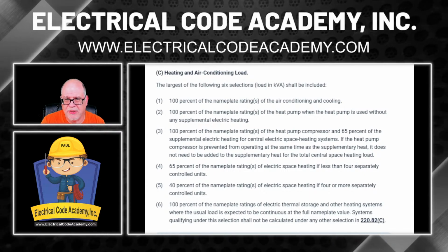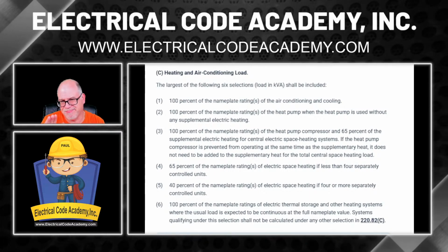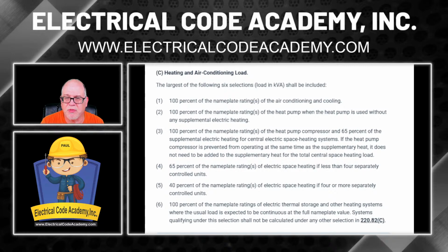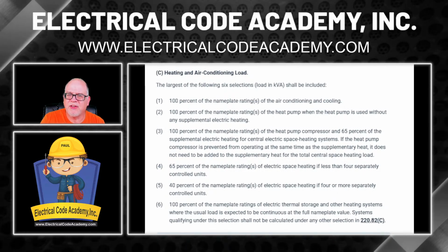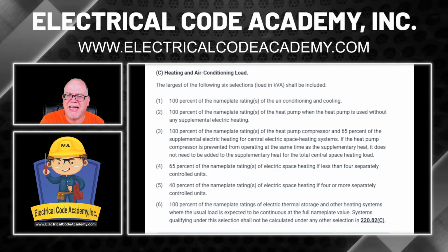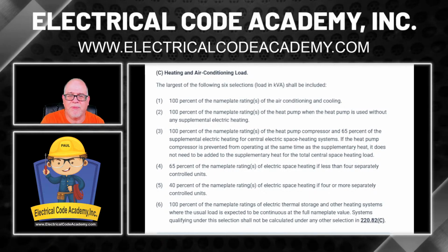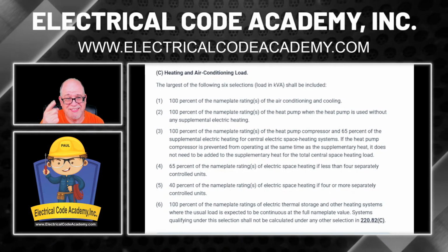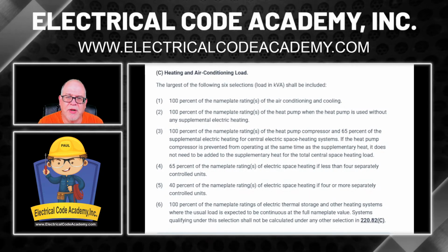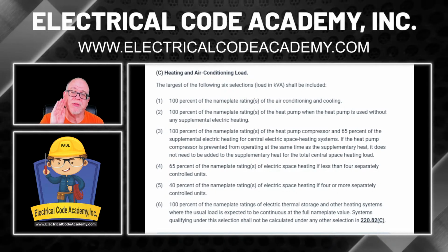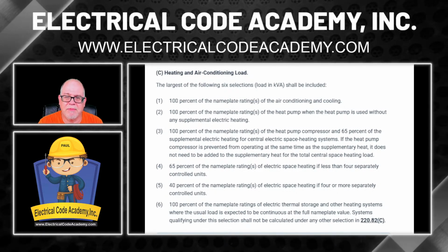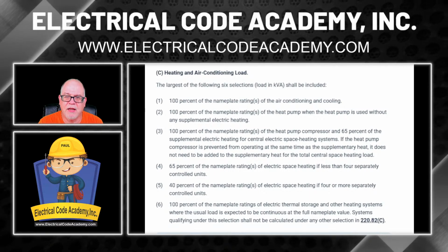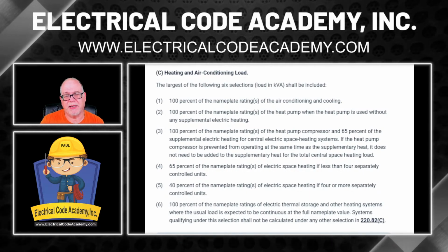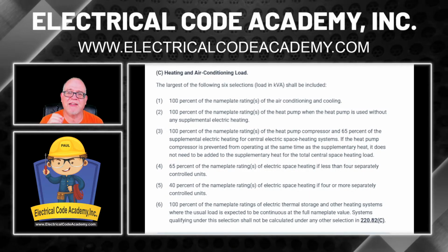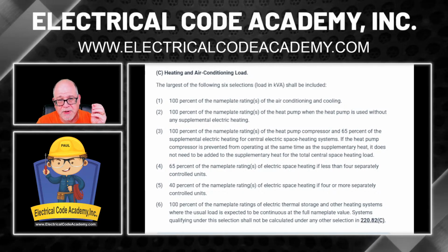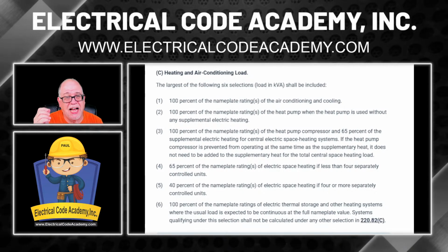Now, looking down the list here, number 2 is a heat pump. Number 3 is still talking about heat pumps. Number 4 is 65%, but that's electric space heating when you have less than 4. Well, we had 6, remember? We had 6. So then we have number 5. Number 5 says 40% of the nameplate rating of electric space heating if there are 4 or more separately controlled units. Well, we had 6. So obviously, we're going to be comparing number 1 for AC versus number 5 for the heat.